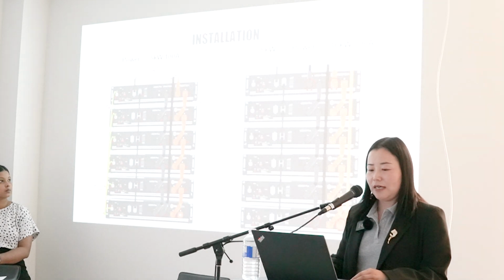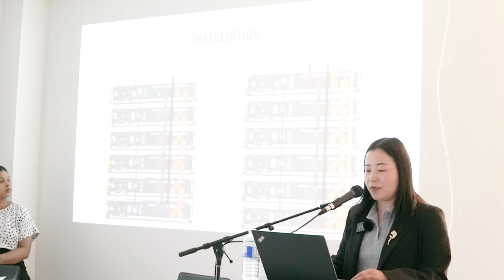So when you do the power connection, if the system is less than 5 kilowatt, the current is less than 100 amp, just use one pair of power cable, but please make sure that one positive and one negative go from the top and one from the bottom. If the power is between 5 kilowatt and 10 kilowatt, 200 amp, add another pair of power cable to distribute the current, because the max current in one cable is 100 amp.